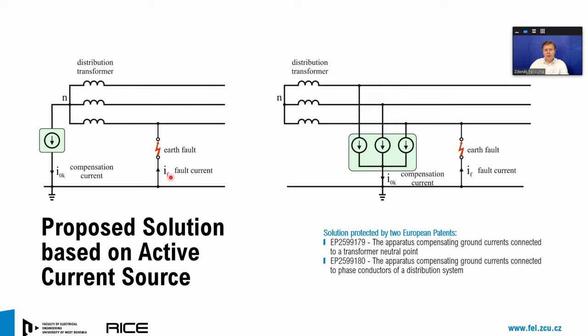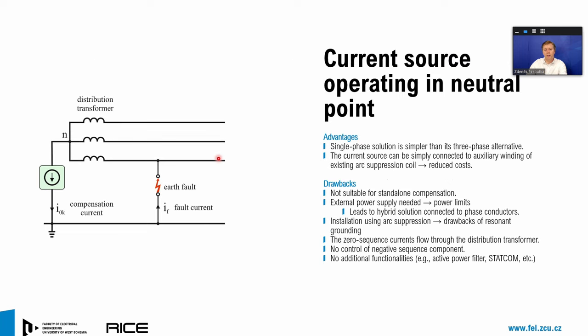We came up with two fundamental ideas for where to connect our fully controlled current source. We covered that with patents. So we have two international patents covering this technology, depending on the location of the current source in the power grid. The first possible location is that we can connect our controlled current source between the neutral point of the distribution transformer and the ground. It is definitely a very cheap solution, and the current source can be simply connected to the auxiliary winding of an existing arc suppression coil, and in this way we do not need to put any transformer into the system, which leads to a further cost reduction.